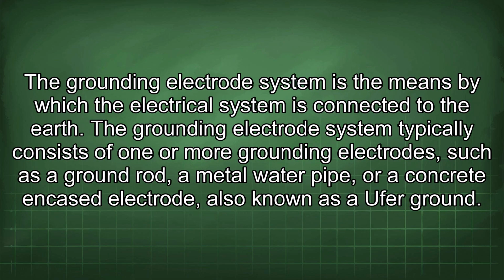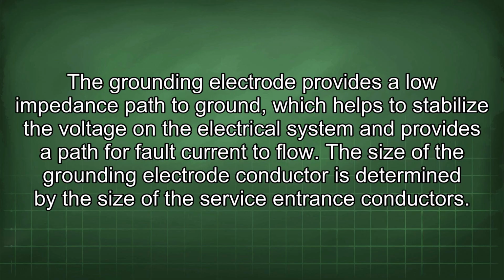The grounding electrode system is the means by which the electrical system is connected to the earth. The grounding electrode system typically consists of one or more grounding electrodes, such as a ground rod, a metal water pipe, or a concrete encased electrode, also known as a Ufer ground. The grounding electrode provides a low impedance path to ground, which helps to stabilize the voltage on the electrical system and provide a path for fault current to flow.